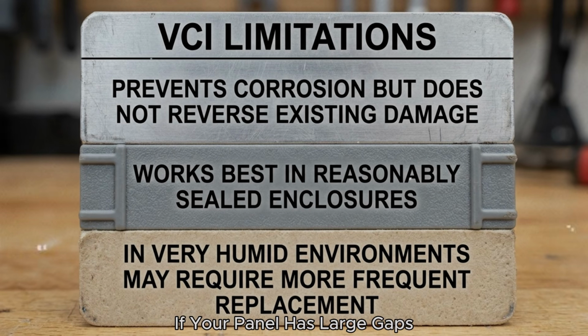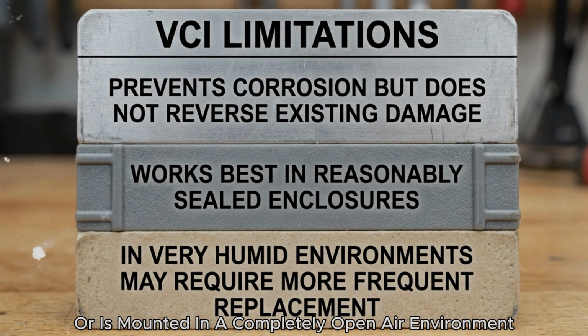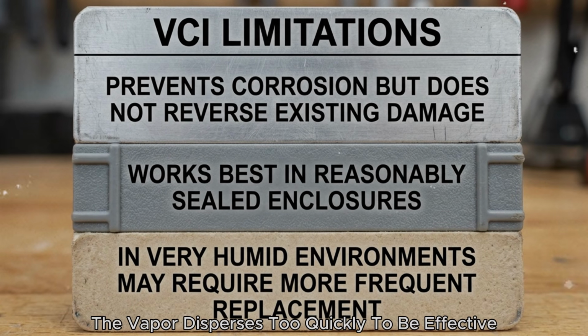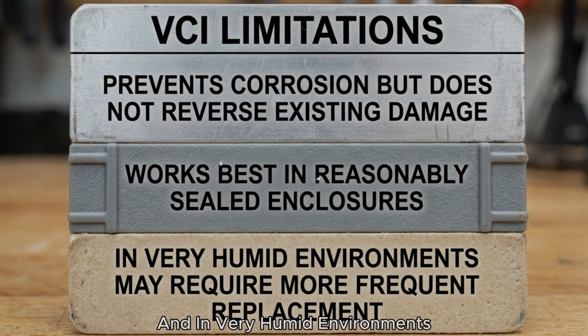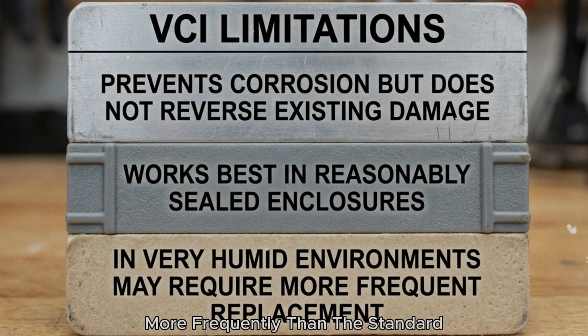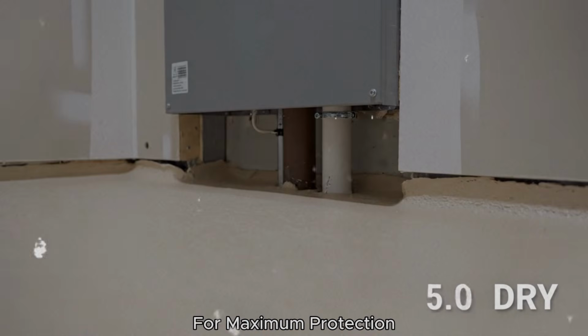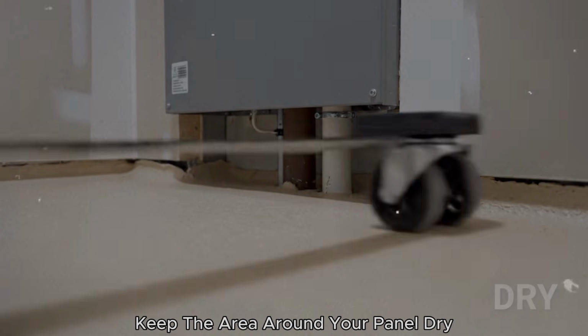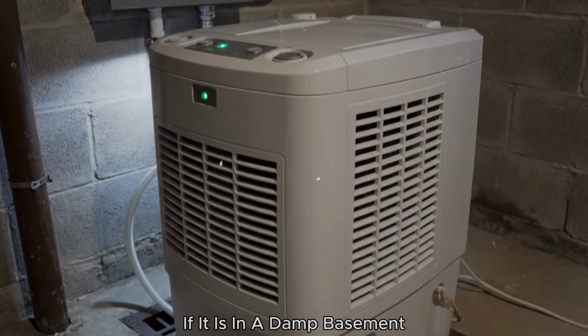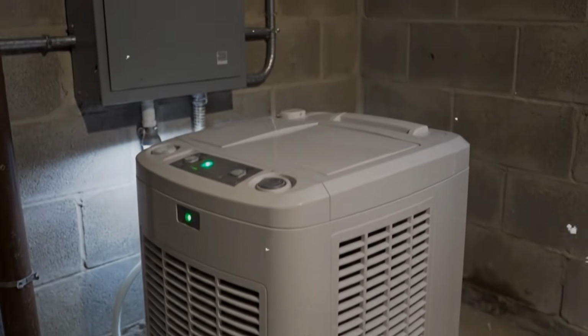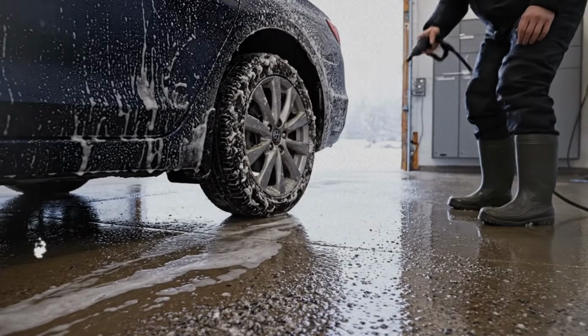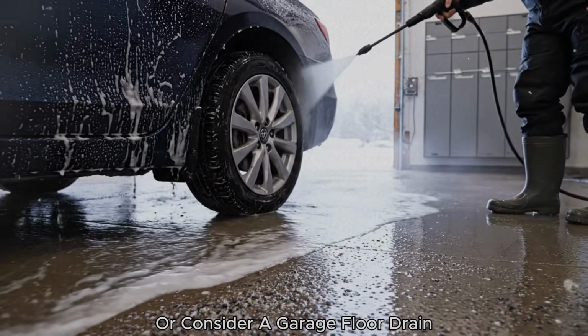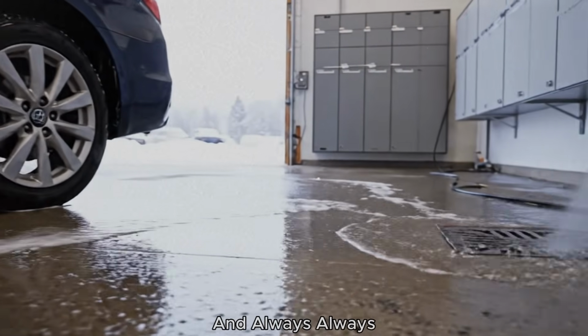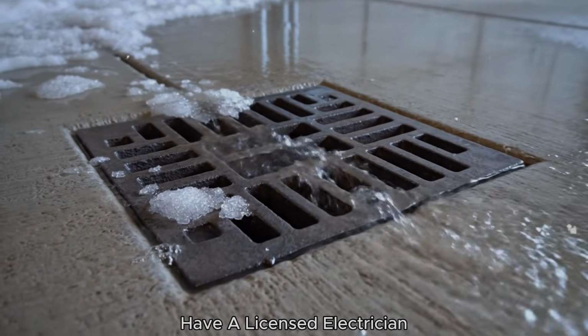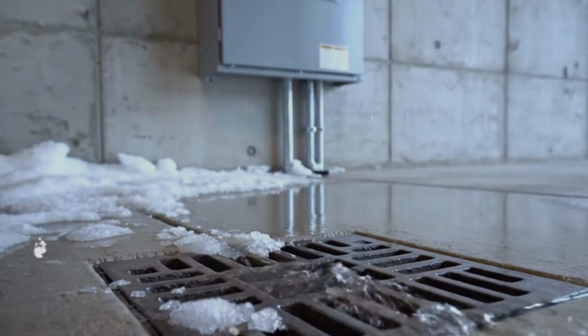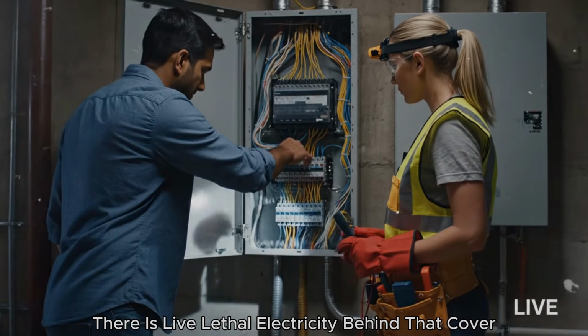If your panel has large gaps or is mounted in a completely open-air environment, the vapor disperses too quickly to be effective. And in very humid environments, you may need to replace the tabs more frequently than the standard 2-year interval. For maximum protection, keep the area around your panel dry. If it is in a damp basement, invest in a dehumidifier. If your garage sees road salt in winter, clear the salt off your car before parking, or consider a garage floor drain. And always have a licensed electrician perform any work inside the panel. There is live, lethal electricity behind that cover.